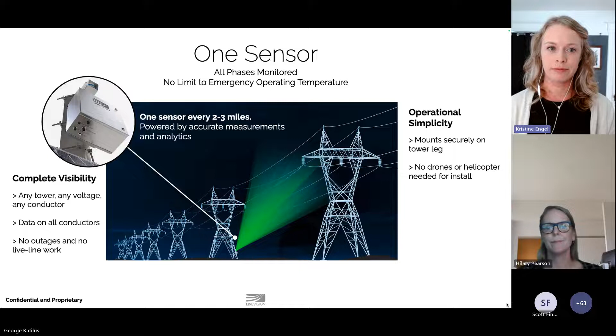Our solution is tower mounted, or structure mounted, I should say. We're agnostic to structure type. It's not installed on the conductor, so that means, very importantly, that no outage is required and no live line work is required, and we're able to monitor different types of conductors at any voltage level. We're not limited by things like the diameter of the conductor. Next slide, please.